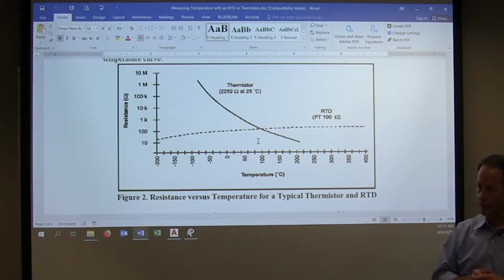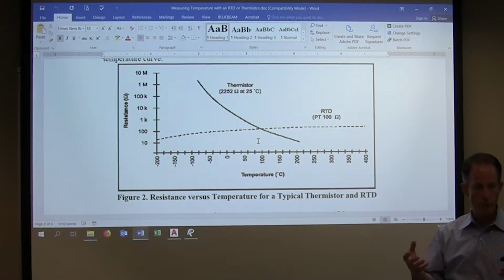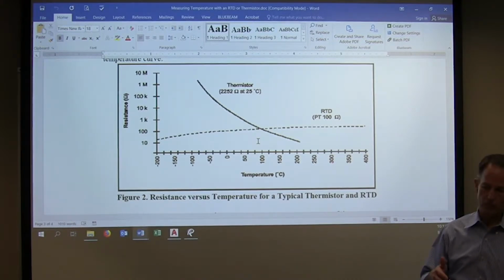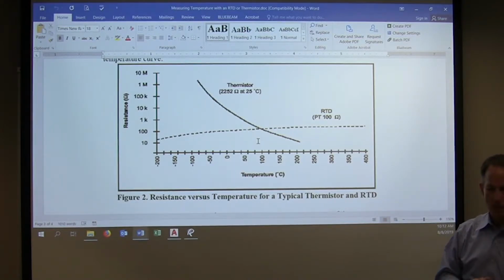What other types of sensors do you guys run into? Well, we've talked about the 2 temperatures that we use. The RTDs are typically for the high precision. The thermistors are for our general use, cheaper, a general range of temperatures, you know, 0 or minus, even 0 degrees Fahrenheit to 100 degrees Fahrenheit, kind of that range. What other sensors do you see out there?